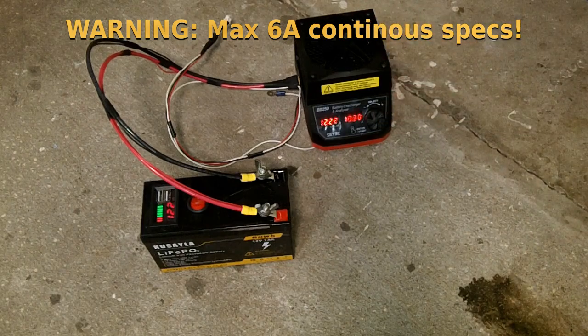Okay, it's ramping the amps up. The voltage is sagging, this display's going down. Okay, it is drawing 25. Oh, and it shut off. So the BMS is shutting it off when it gets above the amp draw. It says it could do 30 amps for 5 seconds. I didn't see that happen.